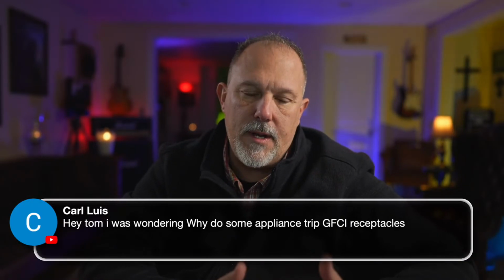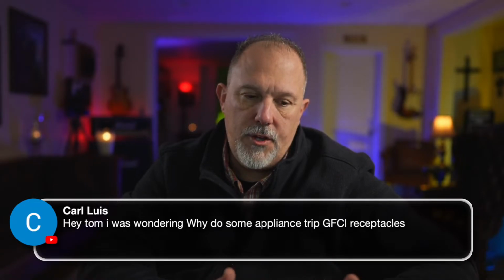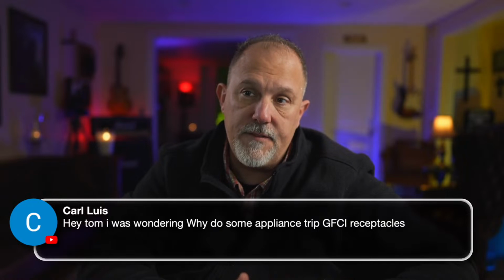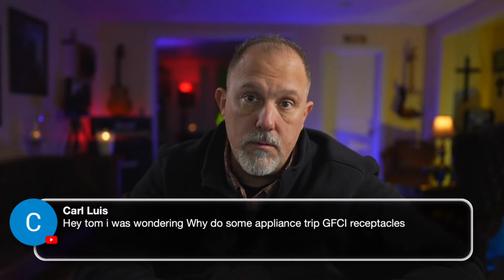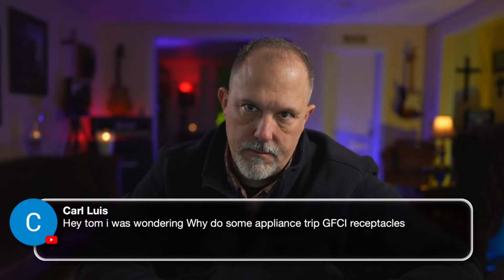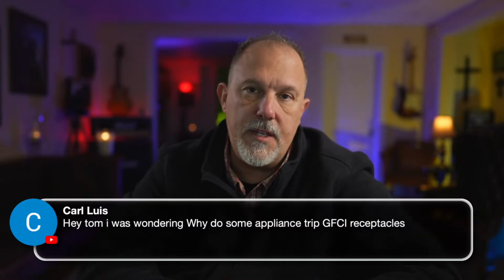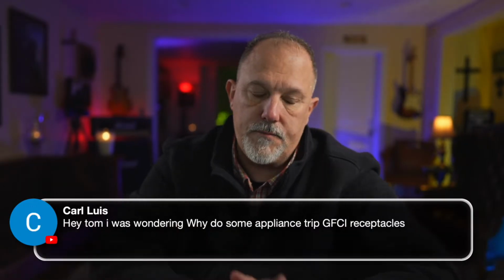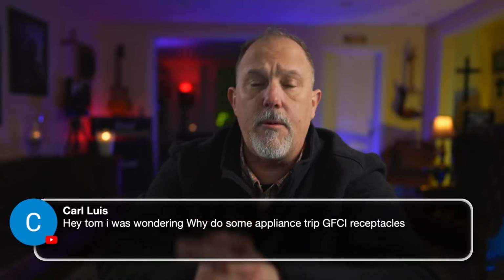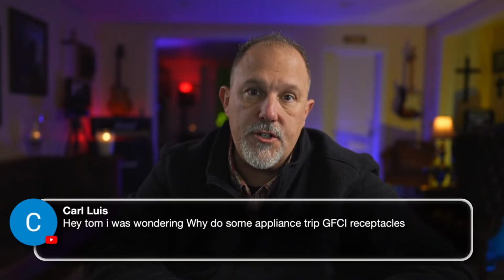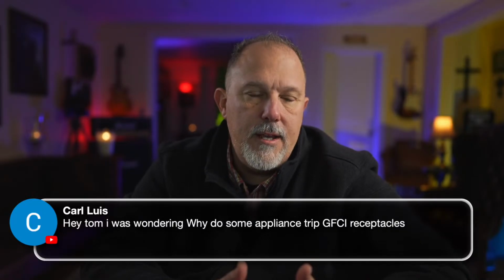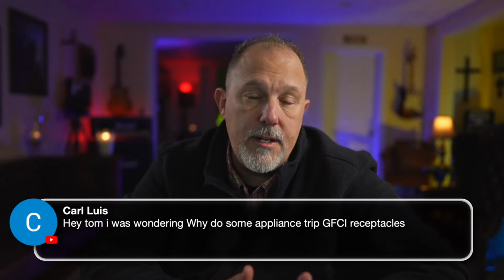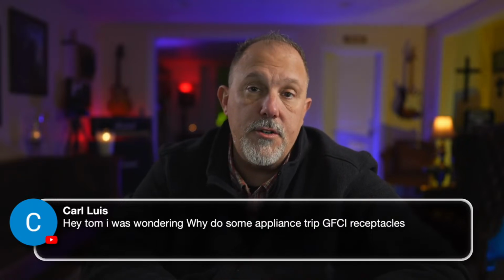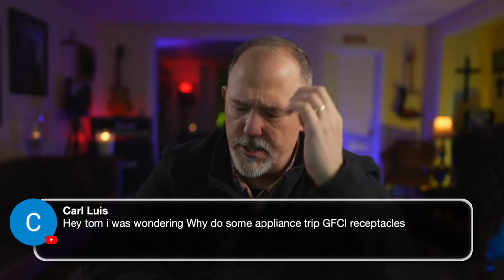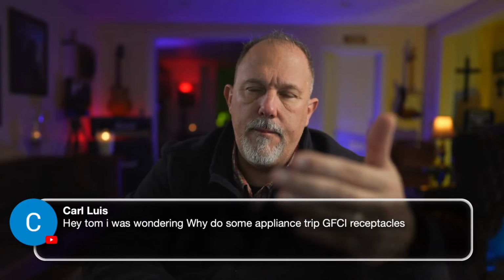Well, when you design a product and you want to filter high frequency stuff, you should filter it to the neutral, not the equipment grounding conductor. But in some of these appliances, say, that are 240 volts, which is not what you're talking about, you're talking about 120. But if it's a 240 volt and there's no neutral, they filter it to the equipment grounding conductor.